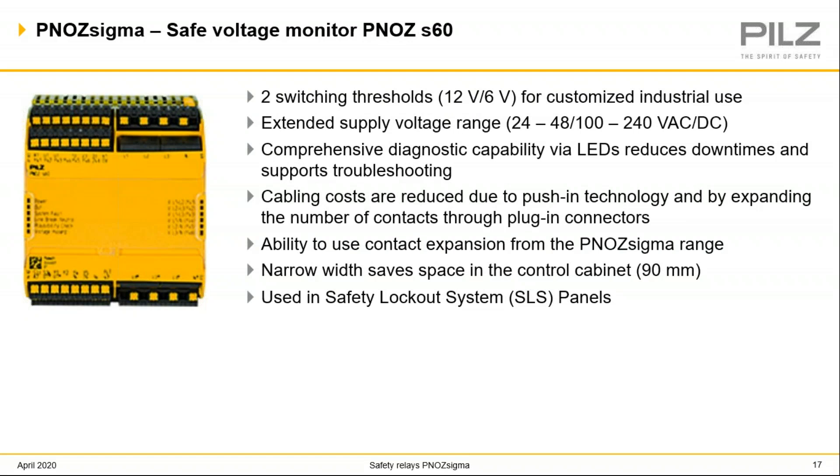The PNOZ s60 is a safe voltage monitor used to monitor single-phase or three-phase power supplies with no voltage applied with neutral conductor. The S60 voltage monitoring relay prevents the safety contacts from closing until it's guaranteed that the plant has no voltage applied. As soon as hazardous energy is detected, the safety contacts are opened, which prevents exposure to the hazardous energy. PILZ uses these in safety lockout system panel applications — and the SLS panels will be the topic of an upcoming training session. Please make sure to register and attend that session to get more information.